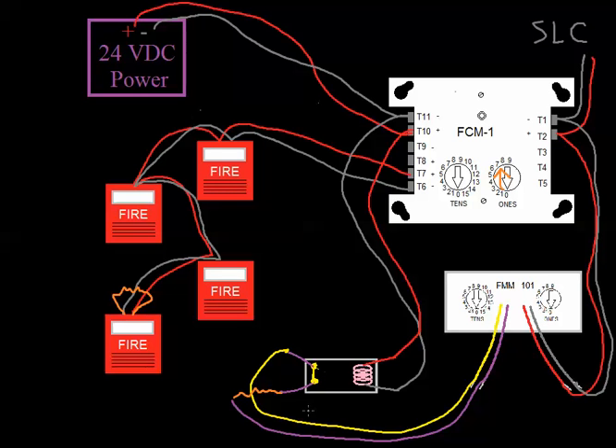And again, in new applications, you rarely have to do that because of the supervision on terminals 10 and 11 on the control module. It'll internally supervise that power, which, as you can imagine, saves a ton of time when you're setting these things up. In some cases, you don't have to pull an extra circuit. If you had a strip mall application where there were control modules in every suite, at the end of that power run, you'd have to have these power supervision relays and monitor modules and everything else, and it's a pain. And so the new application with the firmware is a pretty nice update.